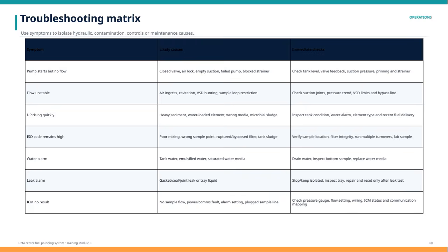For example, if the pump starts but there's no flow, this might be caused by a closed valve, an air lock, an empty suction line, a failed pump, or a blocked strainer. Immediate checks should include verifying the tank level, valve feedback, suction pressure, and ensuring the pump is properly primed, along with checking the strainer for blockages. If you notice unstable flow, potential causes could be air entering the system, cavitation, variable speed drive hunting, or a restriction in the sample loop. It's important to inspect suction joints, monitor pressure trends, check the VSD limits, and verify the bypass line.